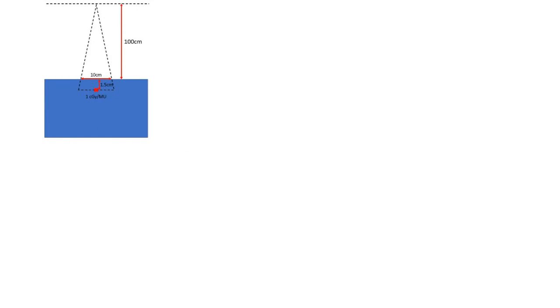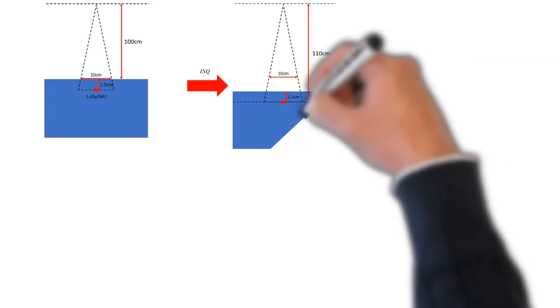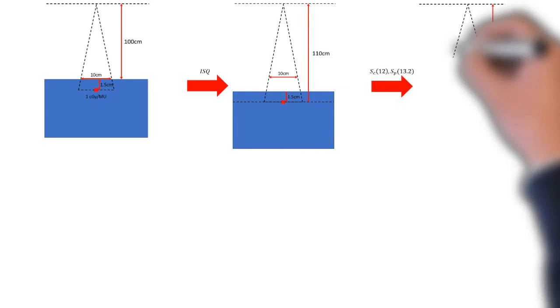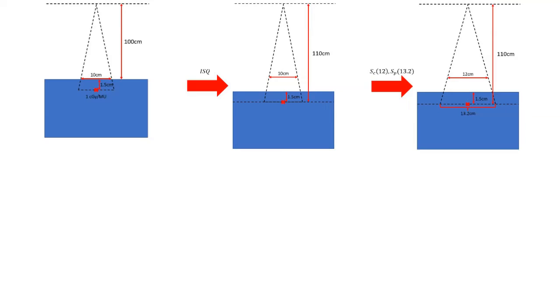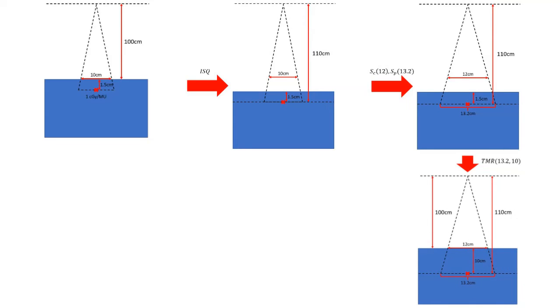We can go ahead and draw out our geometry again. Here's our reference condition: we know that the linac is delivering 1 centigray per MU at a 100 centimeter SSD, field size of 10 by 10, a depth of dmax which is 1.5 for 6x. Then we can apply our inverse square correction, which you see here, so we move from the source to calibration point distance to the distance from source to the calculation point, which is 110 centimeters away since our SSD is 100 and our depth is 10. Now we can apply our scatter factor: the collimator moves to an opening of 12, but remember we need the phantom field size or the field size at the depth of the calculation for the phantom scatter factor, which is 13.2 by beam divergence. Then of course we can change our depth using the TMR for the field size at depth and a depth of 10 centimeters. This is the geometry that we're dealing with now, and this just shows how we are changing our reference dose by applying each of these factors.